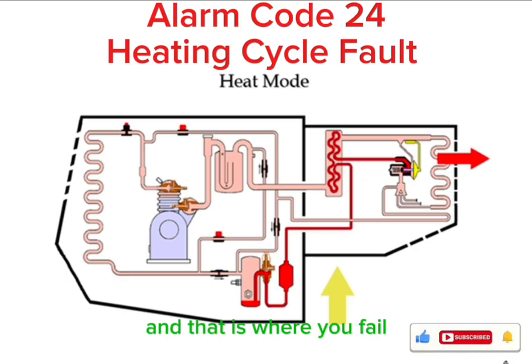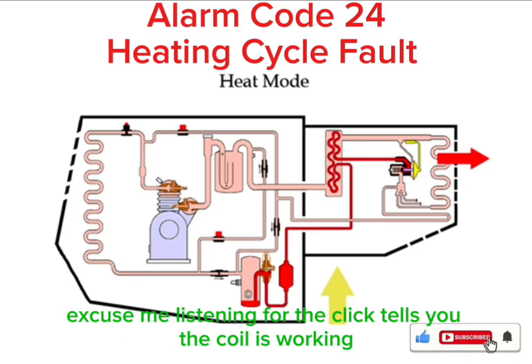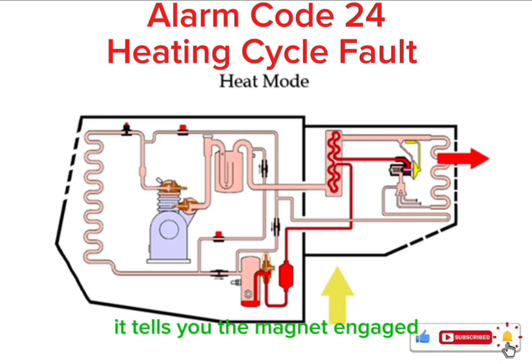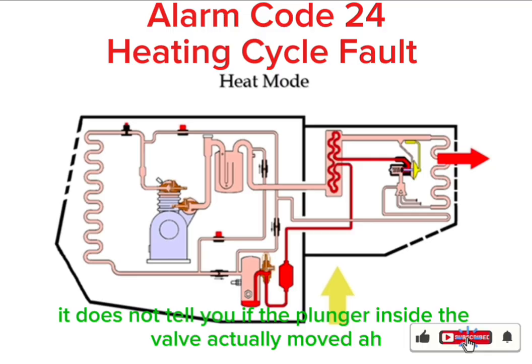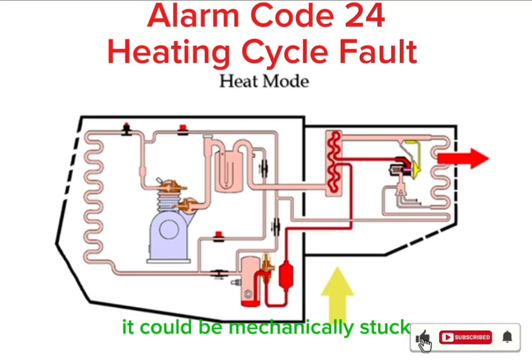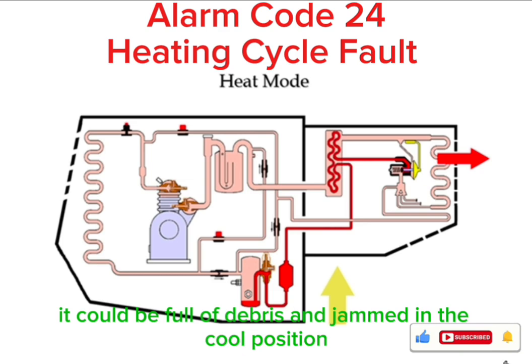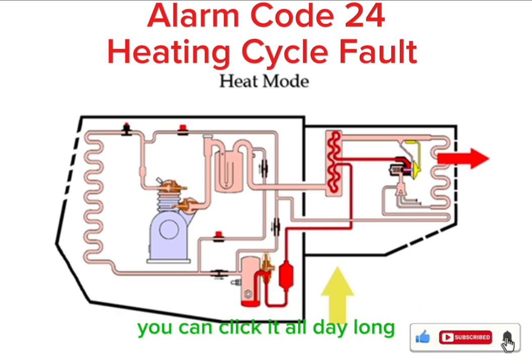And that is where you fail, trainee. What? Excuse me. Listening for the click tells you the coil is working. It tells you the magnet engaged. It does not tell you if the plunger inside the valve actually moved. Ah, it could be mechanically stuck. It could be full of debris and jammed in the cool position. You can click it all day long. You're never getting heat. I see. So electrically it's fine, but mechanically it's a brick. How do I verify the plunger moved?